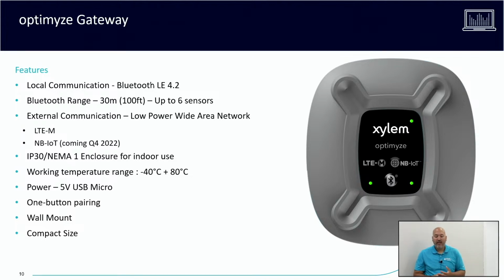Next is the gateway. Once again, this is going to communicate via Bluetooth to the optimyze sensors. You can pair up to 6 optimyze sensors on a single gateway. So the only time you would need more than one gateway is if you can't get all 6 sensors within 100 feet of the single gateway, or you have more than 6 sensors in a single room. Those would be 2 scenarios where you would need to introduce a second or additional gateway to the application.